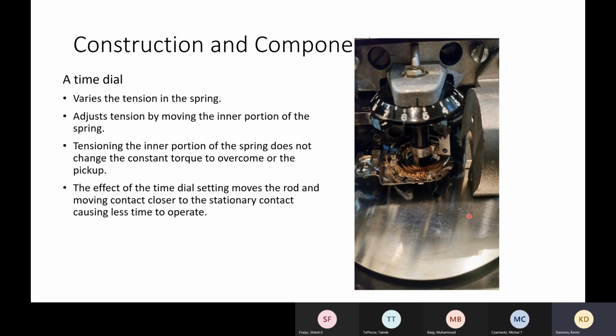So if we exceed a 51 element pickup, what's going to happen is, through the transformer, we're going to induce a torque in this disc, and it's going to turn. Which will then start moving this time dial, this adjustable movable contact. It will start rotating around. And the relay is basically at that point, we call it timing. So it's over its pickup, it's monitoring the current. When it comes around, if it gets to its operating curve, my movable and stationary contacts come in contact with each other. Again, this copper is connected to it. That completes my DC circuit, and I energize my trip coil.